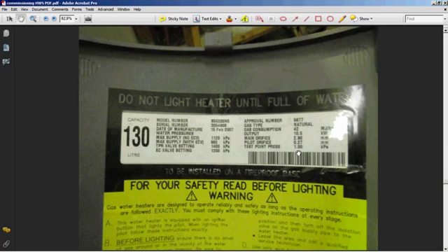you would need to check the supply pressure into the unit to make sure the pipe sizing had been done correctly, or to make sure there were no blockages in the pipeline to reduce the supply pressure. If the supply pressure was correct, the control is faulty and you need to get another control. Always check the supply pressure from that other test point to make sure.